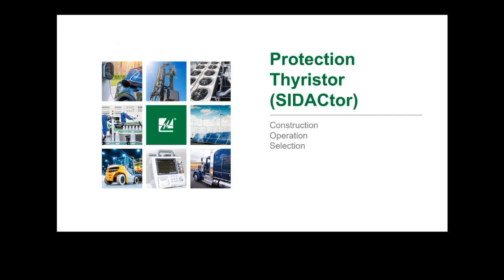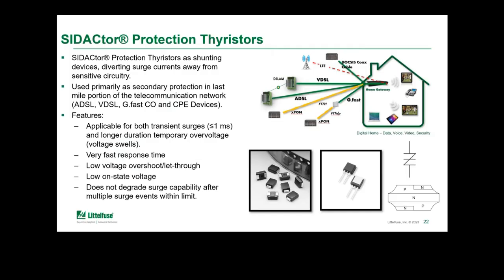The last technology I'll talk about is the protection thyristor, or Sidactor. As mentioned before, they act like a crowbar device similar to a GDT, and they're basically a self-gating triac device. Historically, these have been used in telecom systems to help protect customer premise equipment or central office equipment, to deal with the last mile, where you're running copper from a distribution point that is susceptible to transient or lightning events for end equipment.